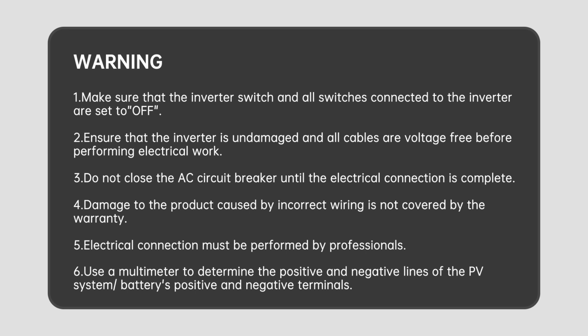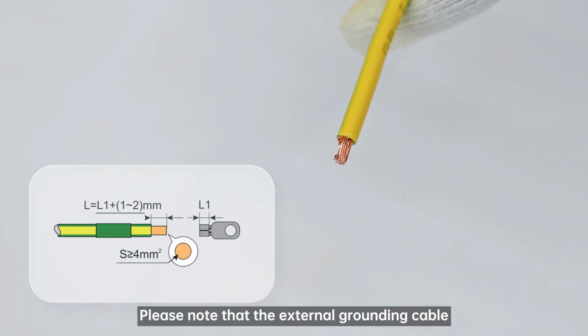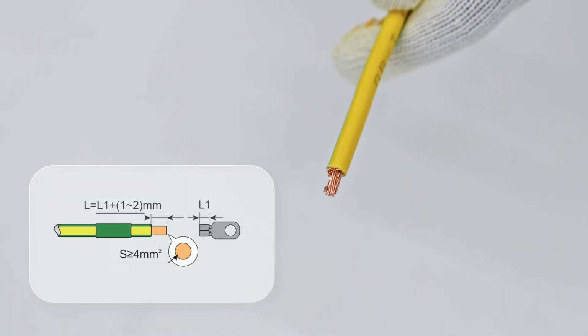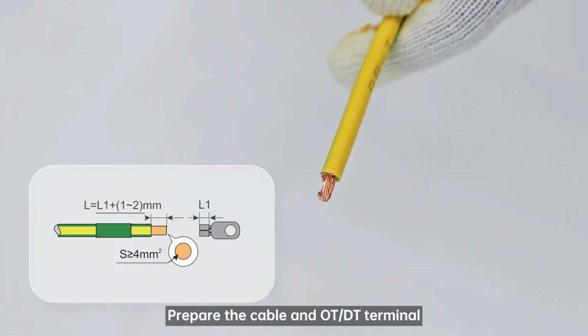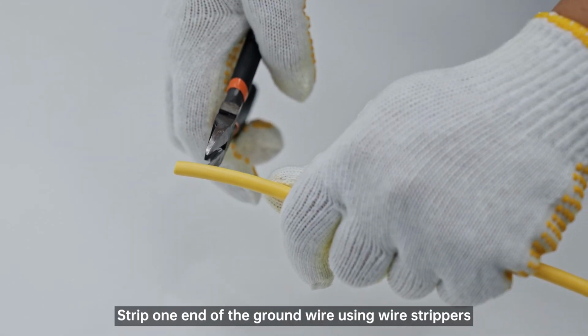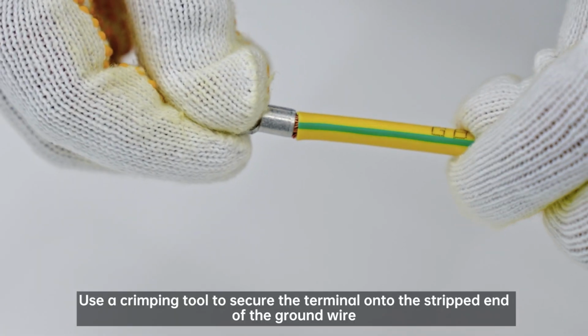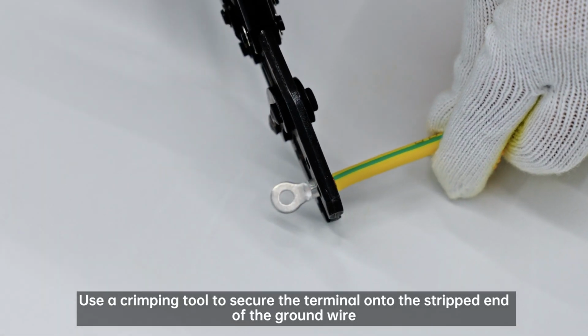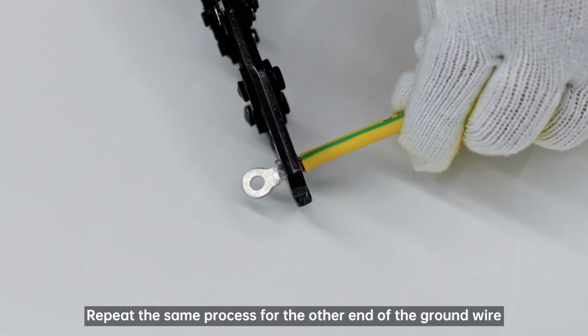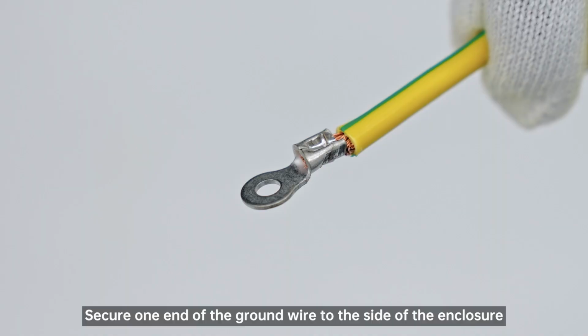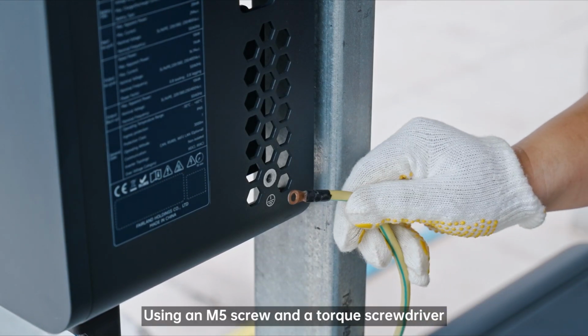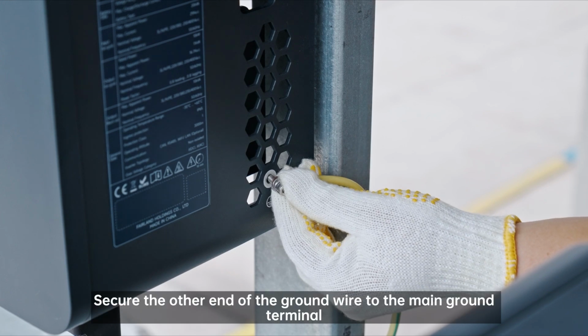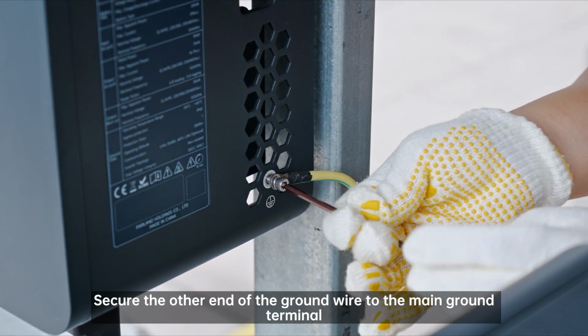Use a multimeter to determine the positive and negative lines of the PV system, as well as the battery's positive and negative terminals. Please note that the external grounding cable needs to be prepared by the customers. Prepare the cable and OT or DT terminal. Strip one end of the ground wire using wire strippers. Use a crimping tool to secure the terminal onto the stripped end of the ground wire. Repeat the same process for the other end of the ground wire. Secure one end of the ground wire to the side of the enclosure. Using an M5 screw and a Torx screwdriver, secure the other end of the ground wire to the main ground terminal.